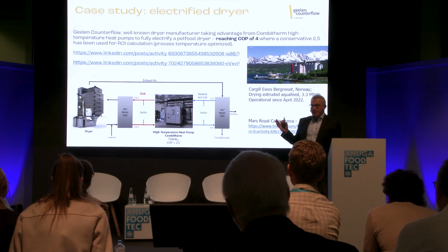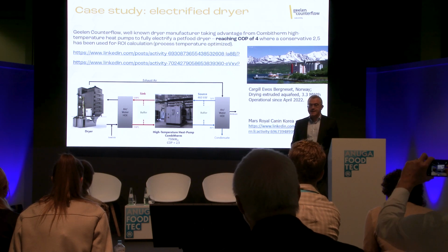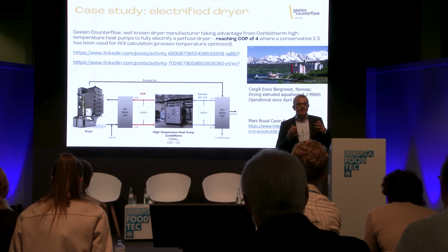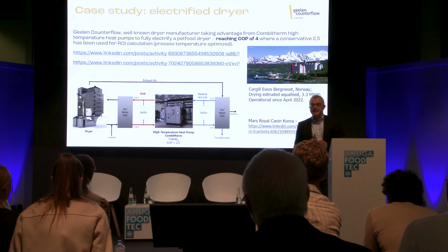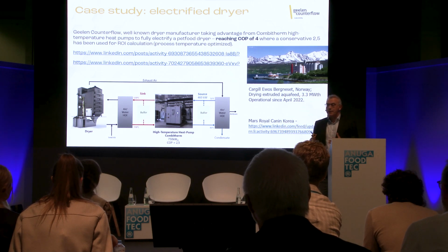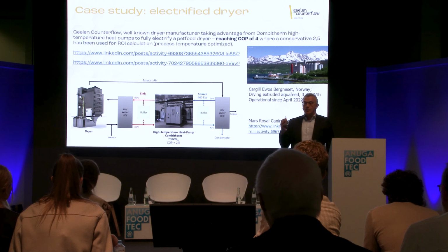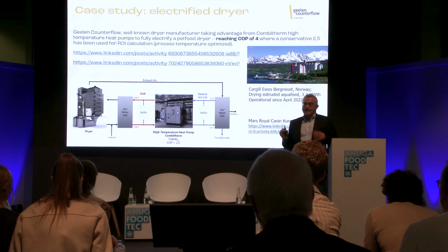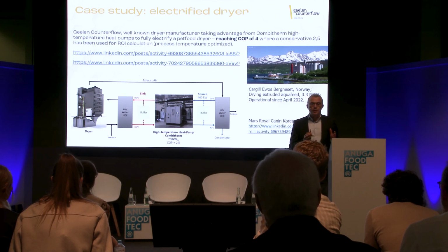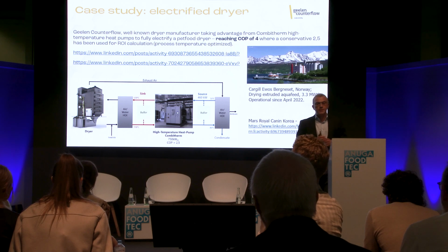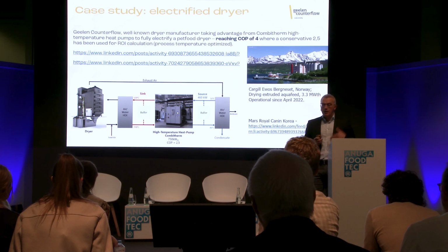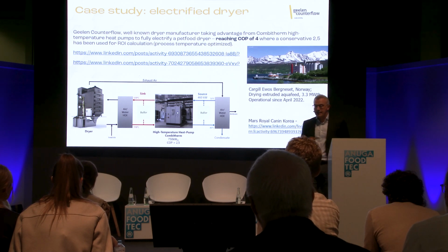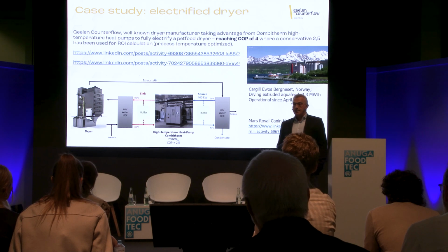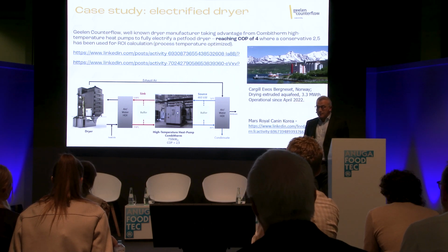The principle is the one I just showed you: the recovery of the exhaust air, the condensation of the air. We want to get the latent heat, not just stay in sensible heat territory. We need the energy in the latent heat, so we need to condense the stack. Then this energy is now hot water that can be stored, used, and upgraded by the heat pump, which goes up to 120 degrees and allows drying the product again and heating the air.